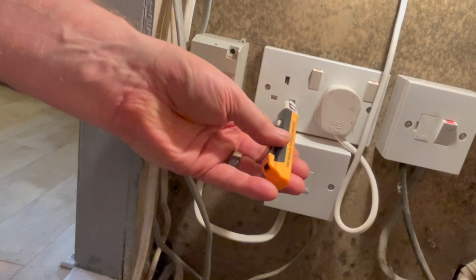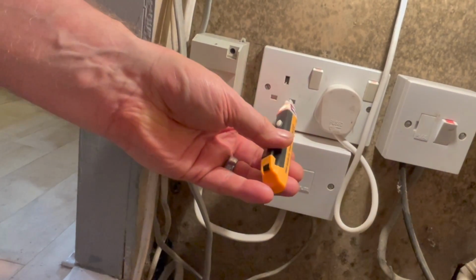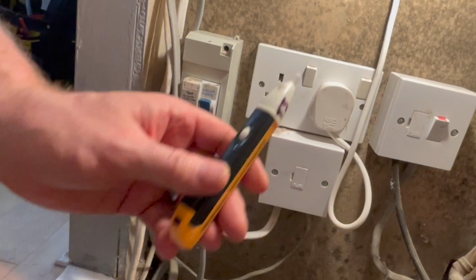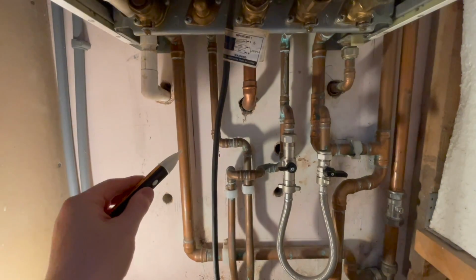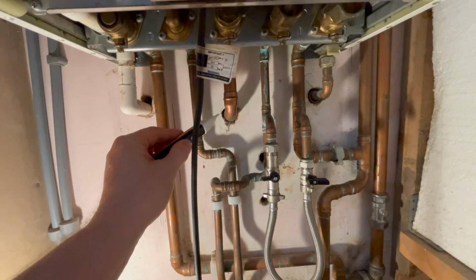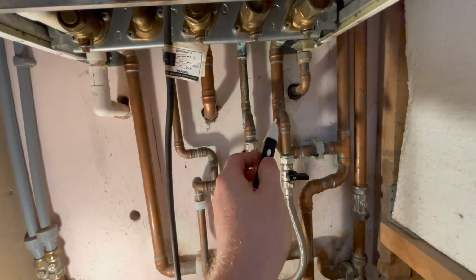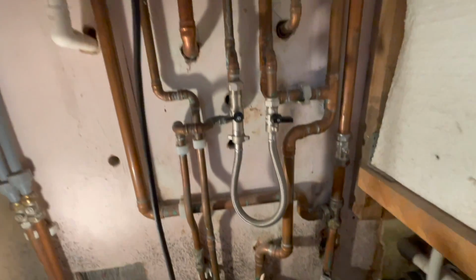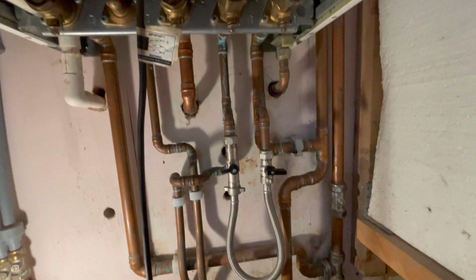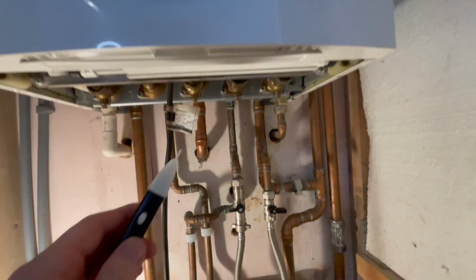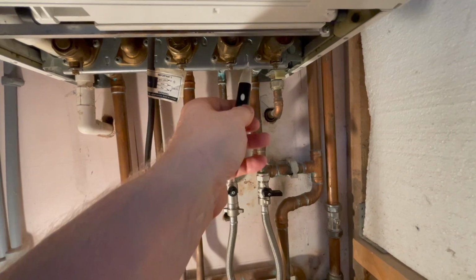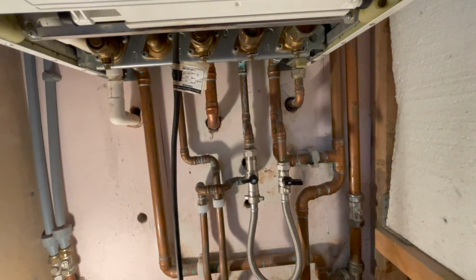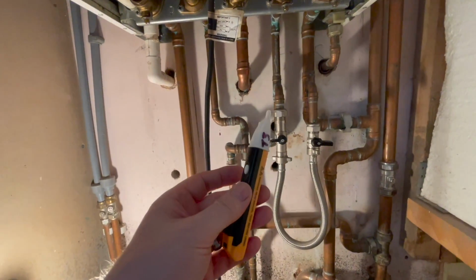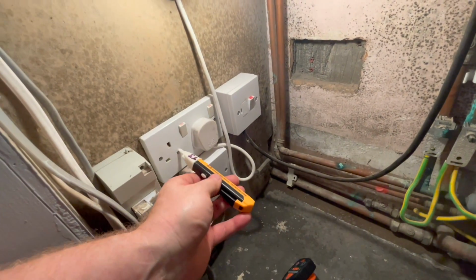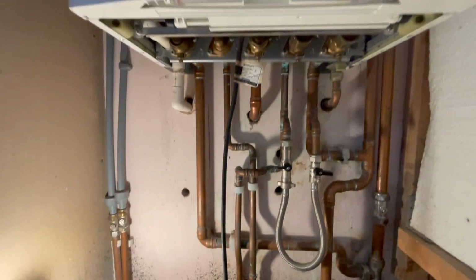So I'm going to put it in the live supply, and you can hear and see that this is working. I can now test the pipe work in the boiler. So while we're under the boiler, I'll just test the pipe work to make sure nothing is live. Not the best pipe work in the world, but there you go. That's what we've inherited. And we can test the boiler is okay. So, need to now prove that this is still working at my socket, which it is, and so it's now safe for me to take this cover off.